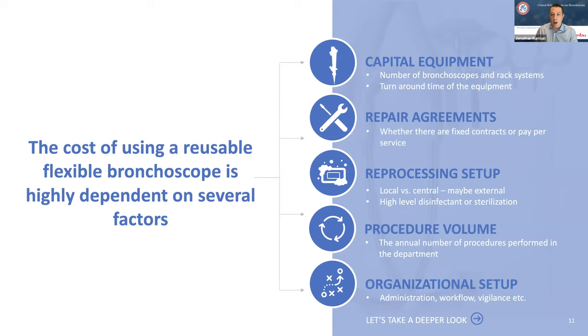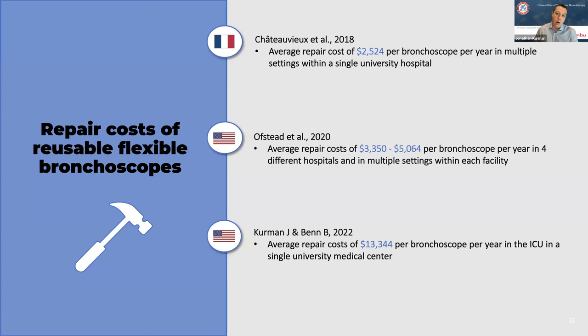Now, I've mentioned the capital equipment expense as well as the reprocessing expense, but another significant expense area is repairs. And this is one that is often underappreciated. More data are emerging on the extent of repair costs, and more importantly, the variability of repair costs. These are three studies over the past 4 years. The first one is from France, and the second two are from the US.